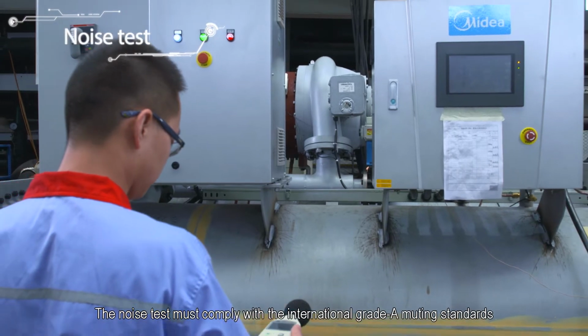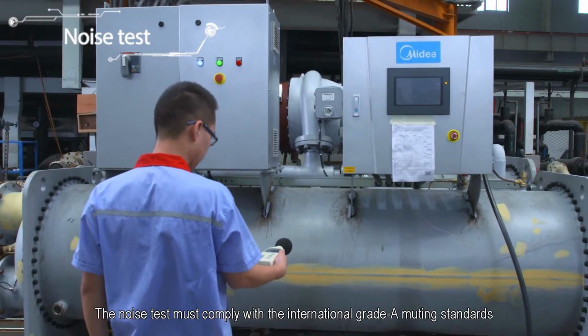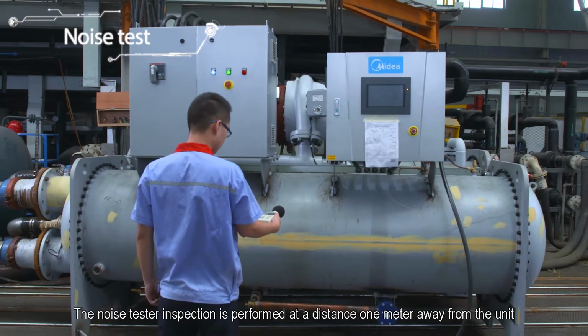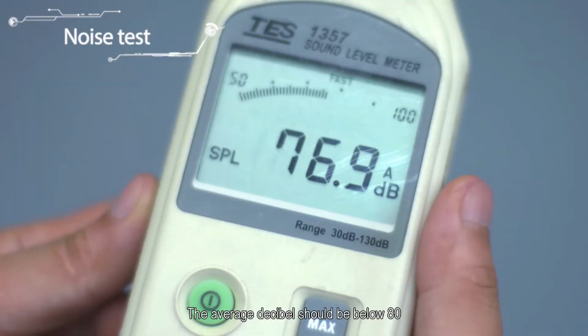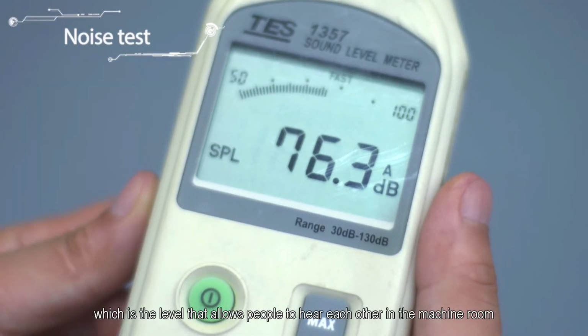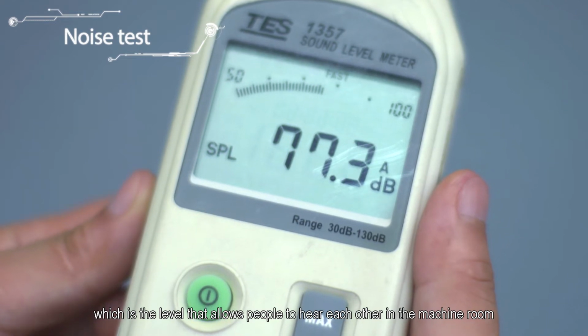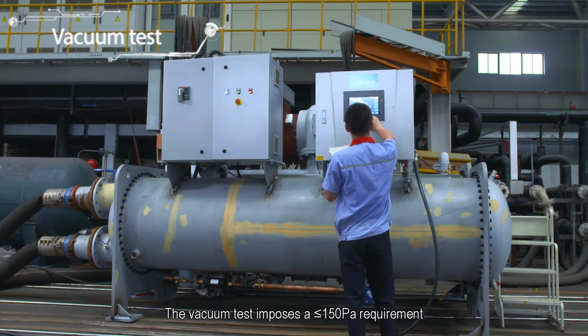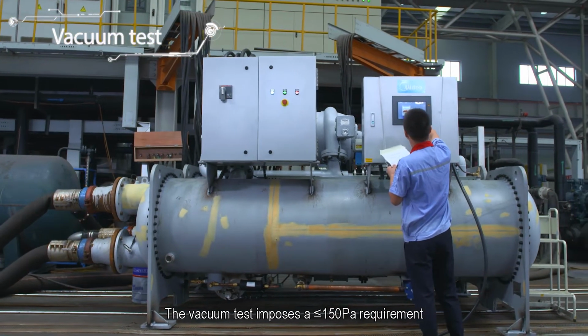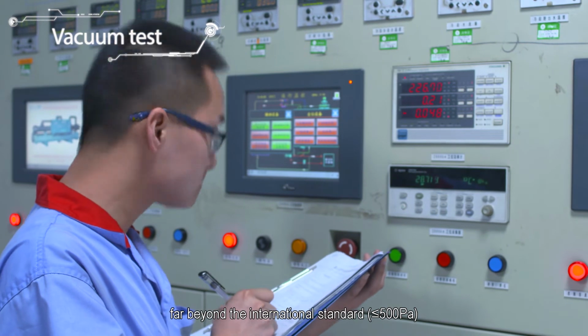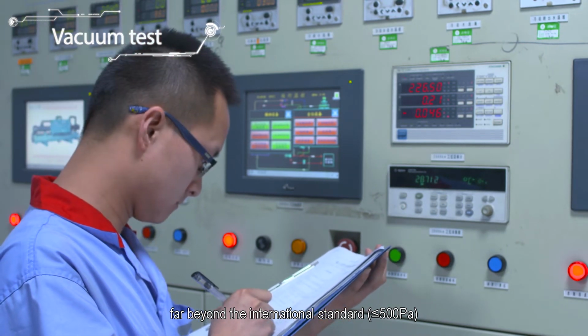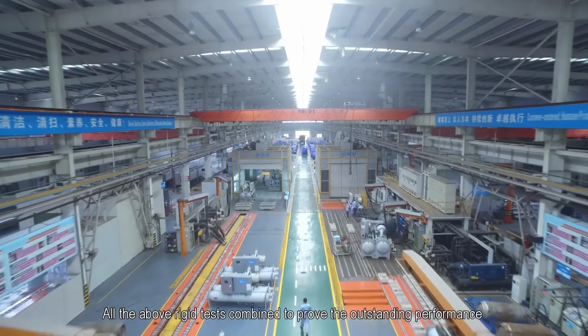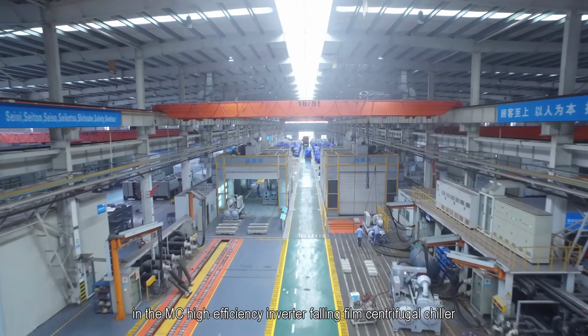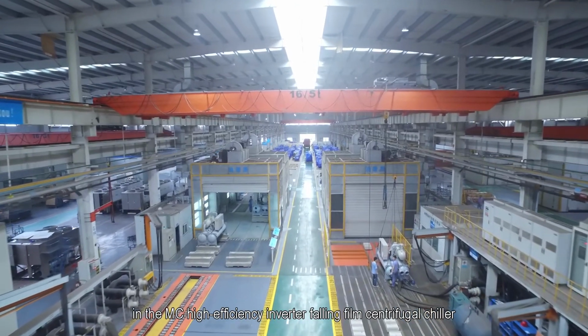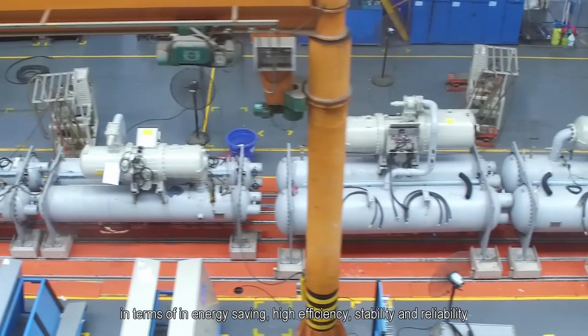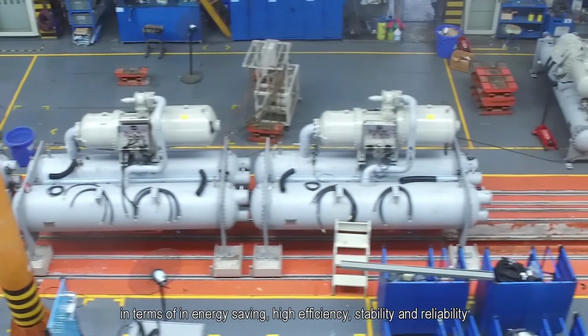The noise test must comply with the international Grade A muting standards. The noise tester inspection is performed at a distance of 1 meter away from the unit. The average decibel should be below 80, which is the level that allows people to hear each other in the machine room. The vacuum test imposes a less than or equal to 150 Pa requirement, far beyond the international standard of less than or equal to 500 Pa. All the above rigid tests combine to prove the outstanding performance of the MC high-efficiency inverter falling film centrifugal chiller in terms of energy saving, high efficiency, stability, and reliability.